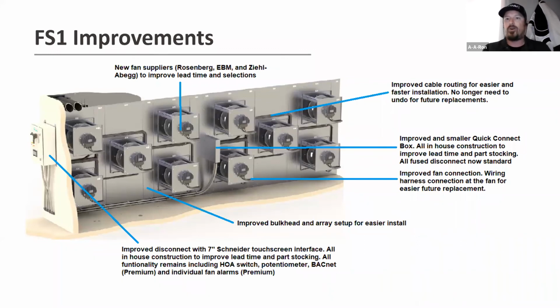We now have all 3 German EC fan suppliers available to us to be able to use and integrate into our BACnet system. Before it was really just 2. Mainly one was our primary supplier, EBM, and the other filled in a few gaps.